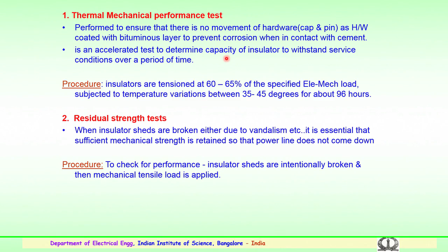To check this residual strength, the insulator sheds are intentionally broken and a mechanical tensile load is applied. The insulator should be able to withstand the load from the conductors and the hardware, and also the load applied on the broken insulators. So, in case the insulator sheds are physically broken due to vandalism, it should be able to withstand for a period of time.